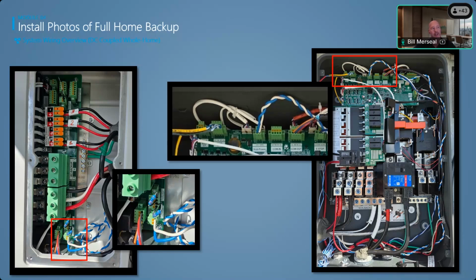This is what I was saying, it depends on if you have a breaker or if it's direct. If you look here on the left, there's a breaker, and you'll notice L2 and L1 are reversed. So when you put a breaker in there, it does reverse polarity. That was L1, L2, so you want to be cognizant of that when you're doing the CTs. That's why we have that sticker, as a reminder: if you're doing a breaker, this is where the CTs should be; if not, this is where they should be. We're trying to make this as easy as possible for everyone.